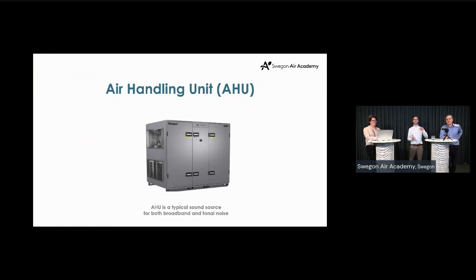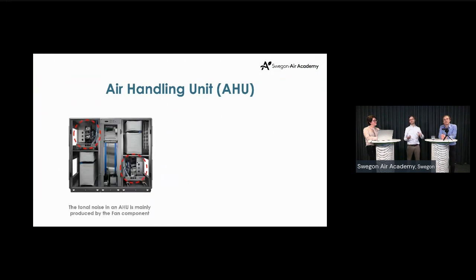An air handling unit is a typical sound source, as we know, both broadband and tonal. It's the fan that produces most of the tonal noise in a ventilation system, and it's also the tonal noise that affects the IEQ and SBS most. So it's important that we can take away these tones.